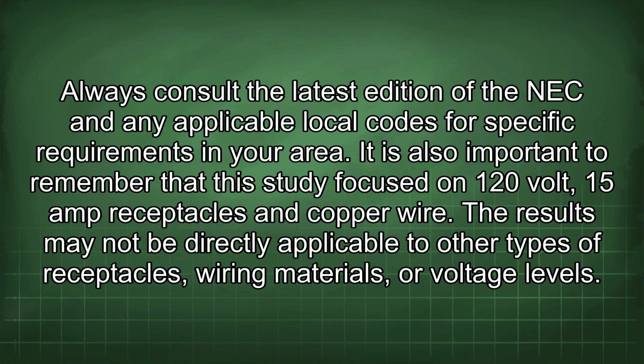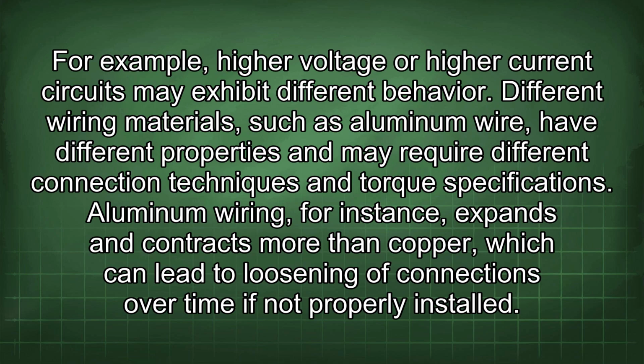It is also important to remember that this study focused on 120-volt, 15-amp receptacles and copper wire. The results may not be directly applicable to other types of receptacles, wiring materials, or voltage levels. For example, high voltage or high current circuits may exhibit different behavior. Different wiring materials, such as aluminum wire, have different properties and may require different connection techniques and torque specifications.